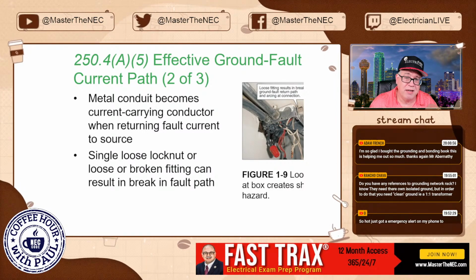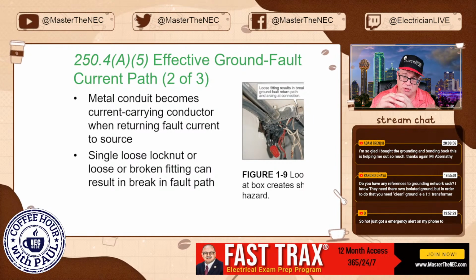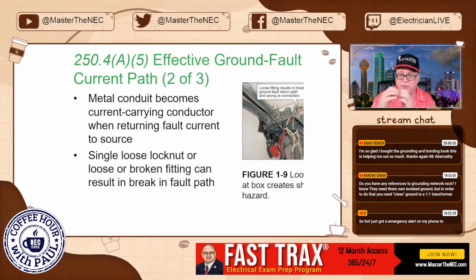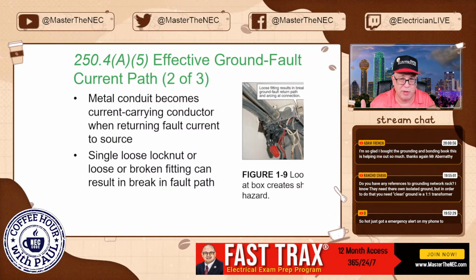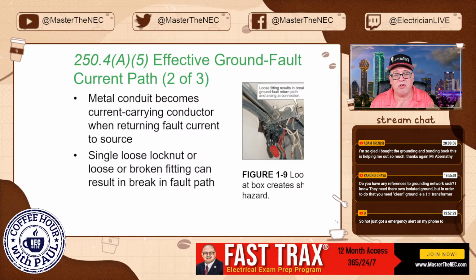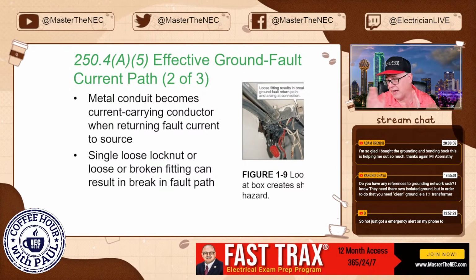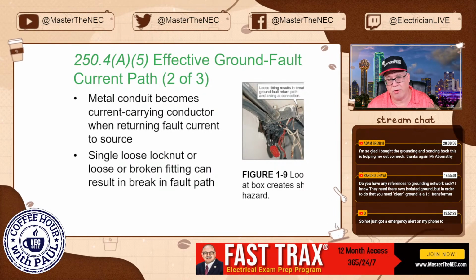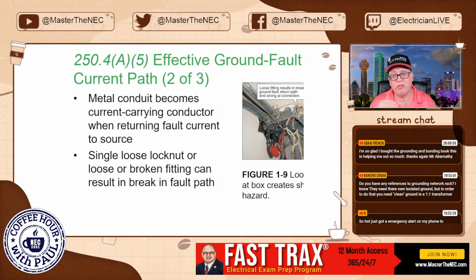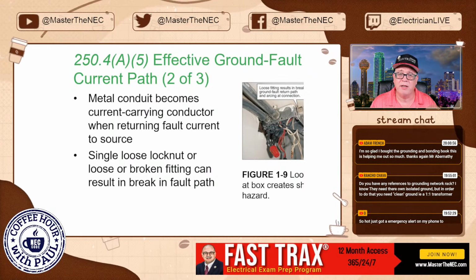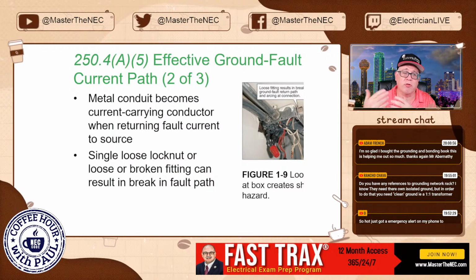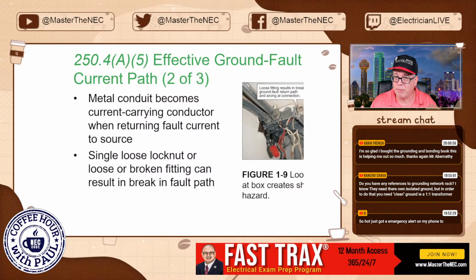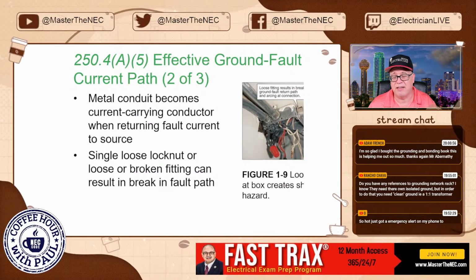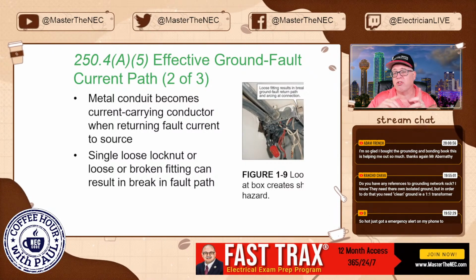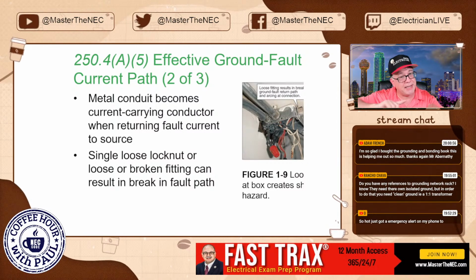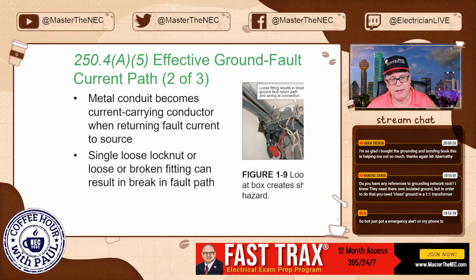But I'm going to tell you, in a fault condition, if it is a loose screw or a loose set screw, it's probably going to fuse and it still probably would clear the overcurrent device. But a lot of engineers don't want to run that risk. They're just like, nah, just put the wire in. I don't want to risk it, okay? But I just want you to know that in a ground fault condition, and you're using the raceway as the equipment grounding conductor, it's going to carry current. Obviously, it's going to become a current conductor when it returns that fault current. And then hopefully it clears and then it opens it up, okay?